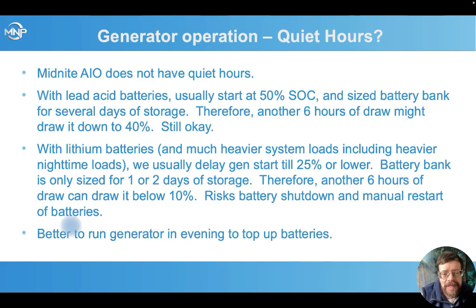When we had large lead-acid battery storage, we would usually set the generator to start around 50%, and that battery bank was often sized for several days of storage. Also, the older systems tended to have fewer loads at nighttime, usually maybe the refrigerator, which might even be on DC power, but not a lot of constant overnight loads. Therefore, another couple hours of draw, if we hit that 50% state of charge where it would normally start the generator, might draw it down a bit more, but still above our minimum allowable draw for a lead-acid battery. So it's okay if we wait a couple hours and then start it in the morning.